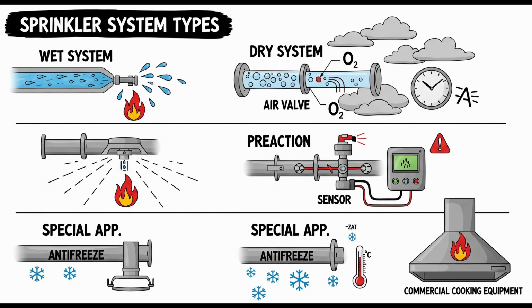Also, a newer requirement, effective January 1st, 2021. If an electric actuator that controls the valve is removed, it must cause an audible and visual impairment signal at the control panel. So you can't just disable the automatic operation without it being obvious. Right. Prevents tampering or accidental disabling going unnoticed.